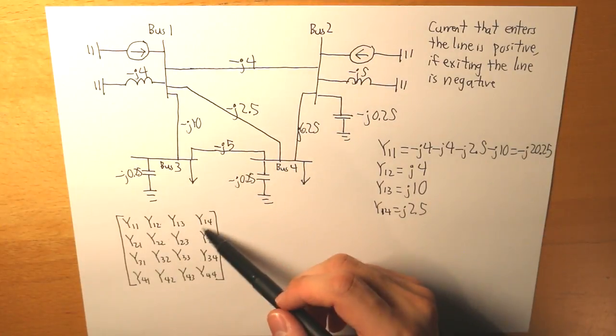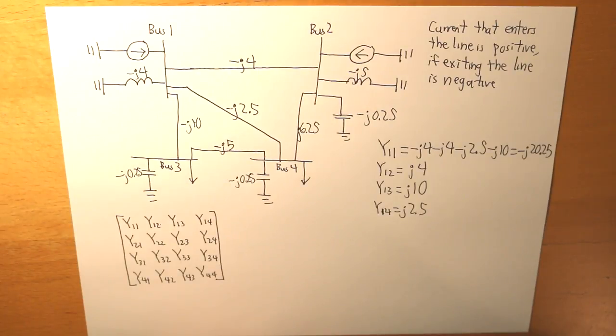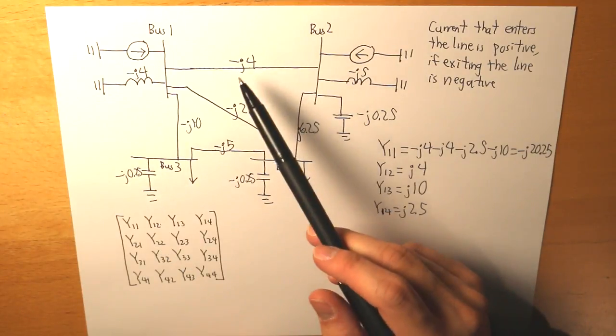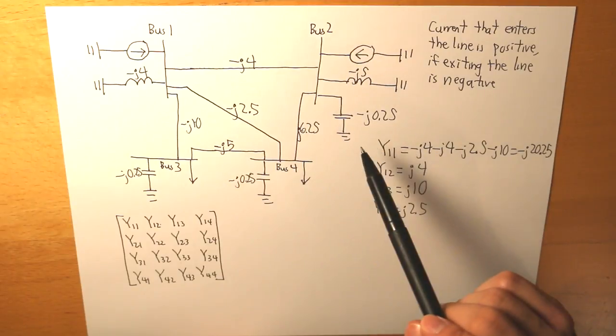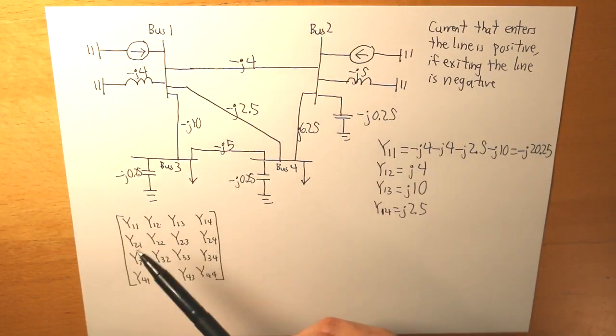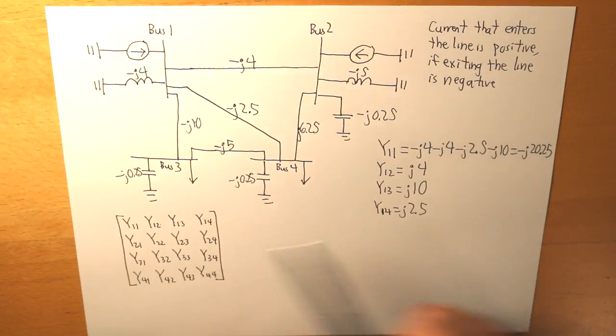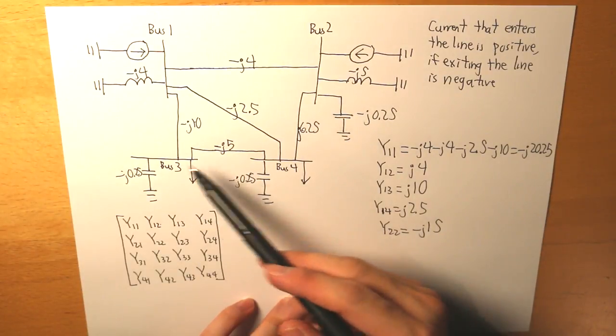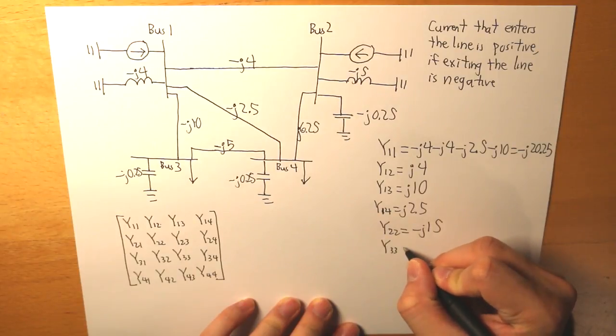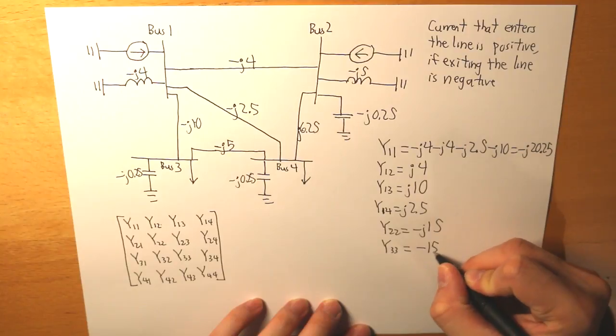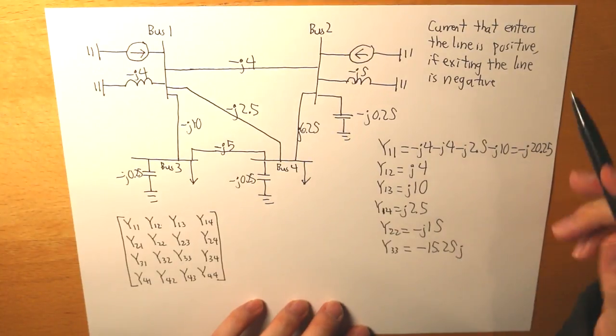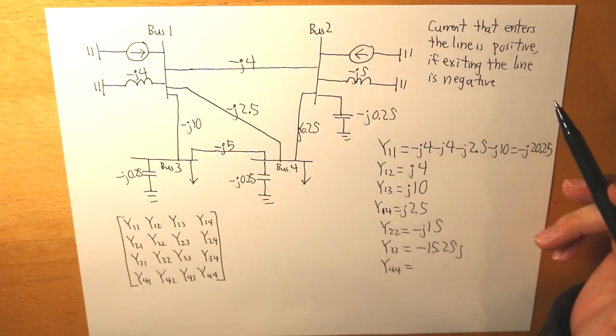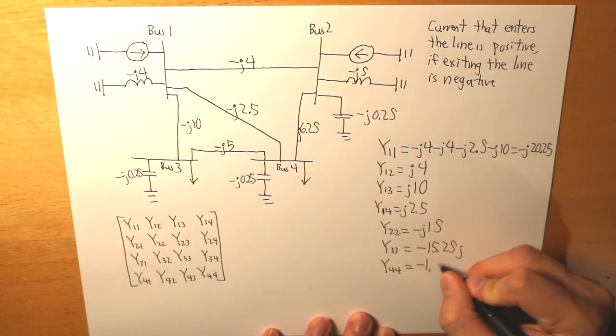For y22, we take all the admittance values connected to bus 2: negative j4, negative j6.25, negative j0.25, and negative j5, giving us y22 equals negative j15. For y33, we get negative j15.25, and for y44, the value is negative j1.5.